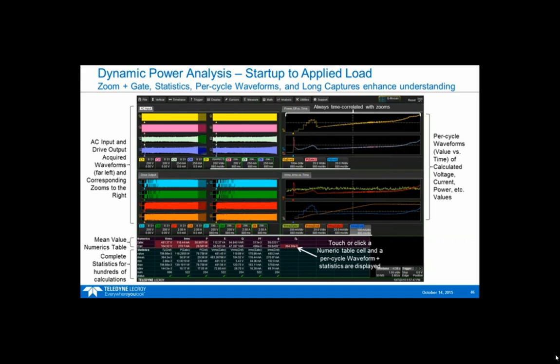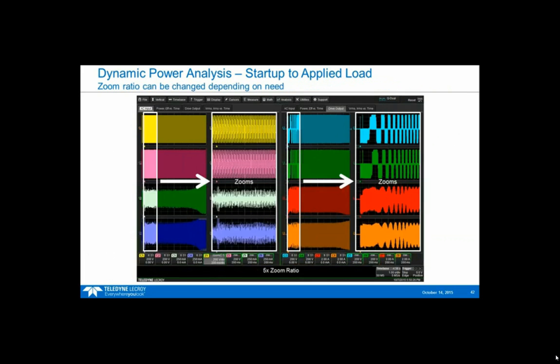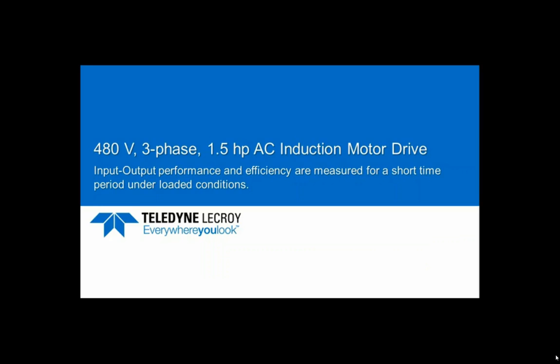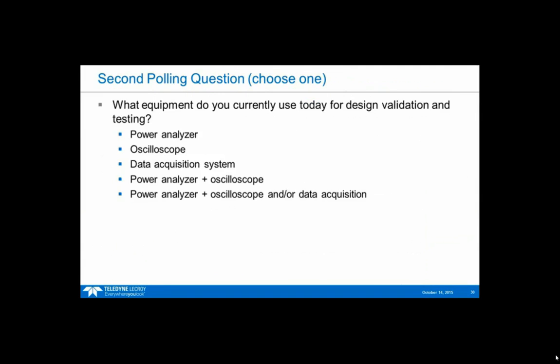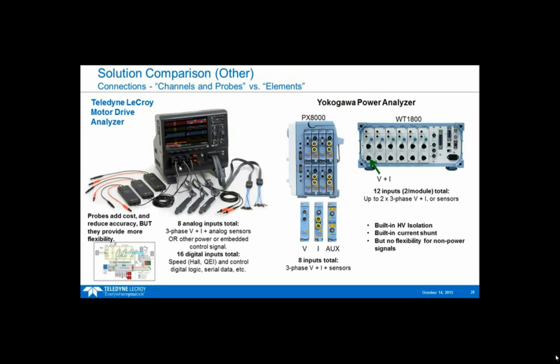Right within the channel menu, you can directly rescale it. So if you take the BNC output and connect it to the channel input on the motor drive analyzer, it's as simple as plugging it into one of these inputs here. Instead of using a probe, you just plug a BNC in from your CT, your Danfysik, or your LEM system. The LEMs are voltage output, I believe, so the scaling is very simple.